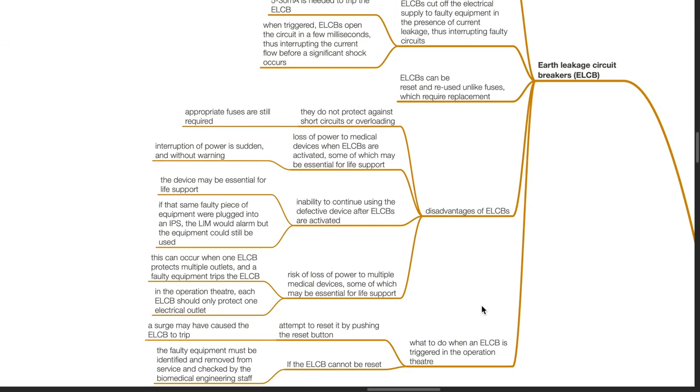Disadvantages of ELCBs: They do not protect against short circuit or overloading; appropriate fuses are still required. There will be loss of power to medical devices when ELCBs are activated, some of which may be essential for life support. Interruption of power is sudden and without warning. Inability to continue using the defective device after ELCBs are activated; the device may be essential for life support. If that same faulty equipment were plugged into an IPS, the LIM will alarm but the equipment could still be used. Risk of power loss to multiple medical devices, some essential for life support, can occur when one ELCB protects multiple outlets and a faulty equipment trips the ELCB.